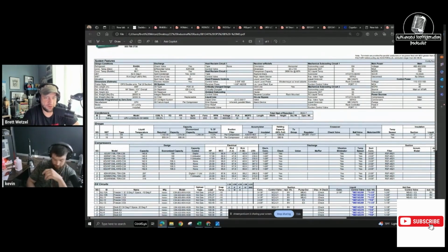There are some things that you can do. Sometimes if you have two condenser fan motors that are sharing the same chamber of air, and one condenser fan motor is out and you can't get that condenser in right now, sometimes you can cover up the other one. If it is sharing the same air chamber and you have that one just sitting there going backwards in the breeze, essentially it's just bypassing the air. It's not pulling the air through the actual coil. It's going to pull the path of least resistance. So just keep that in mind too.